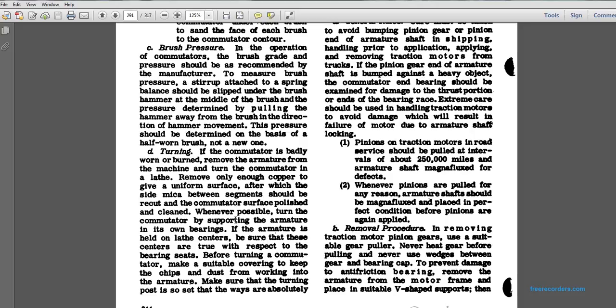Turning. If the commutator is badly worn or burned, remove the armature from the machine to turn the commutator in the lathe. Remove only enough copper to give a uniform surface, after which the sides of the mica between segments should be recut. The commutator surface should be polished and cleaned whenever possible. Turn the commutator supported in the armature's own bearings.